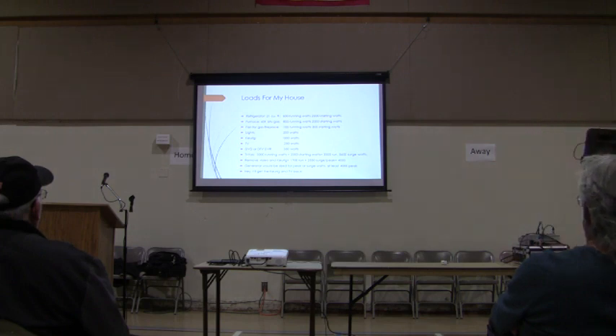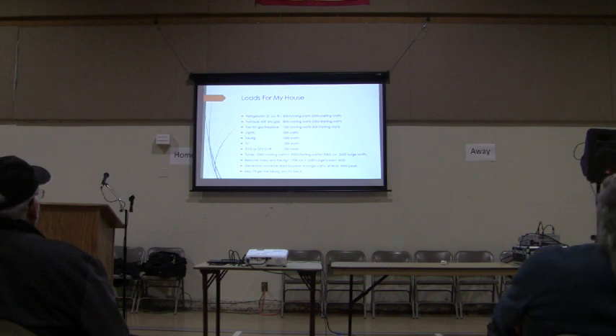So if I add it up, I've got 3,300 running watts — sounds pretty good, right? My highest starting watts is 2,350, from my furnace motor. That gives me a total of 5,650 surge watts. So that's what I'm looking for on the surge number.